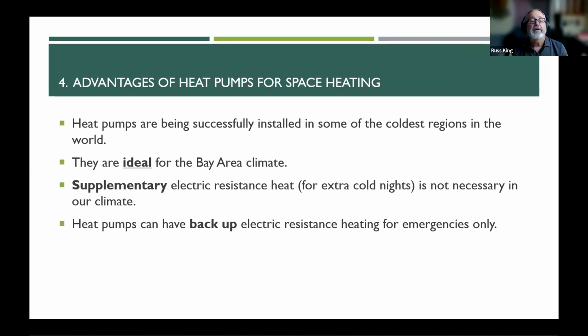In fact, they're ideal for the Bay Area climate, because one of the weird things about heat pumps is that it's an air conditioner and a heater in one unit, and you can't buy one with extra high heating and extra high cooling. The relationship between heating and cooling capacity is always kind of fixed. So climates where the heating load and the cooling load fall into those ranges are the best places for heat pumps. In really cold climates, you might have to oversize the air conditioner. But the Bay Area climate is perfect. Most of Northern California, every place except like Truckee and Tahoe, is ideal for heat pumps.